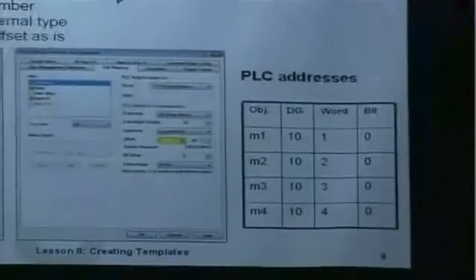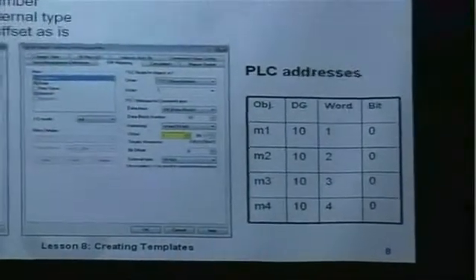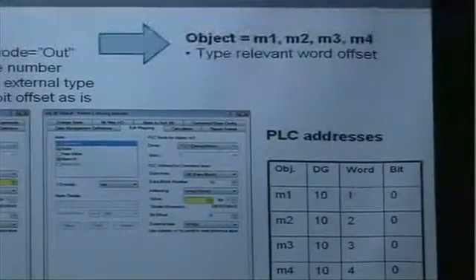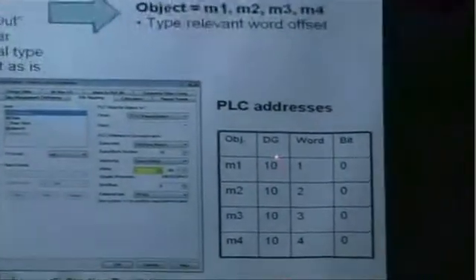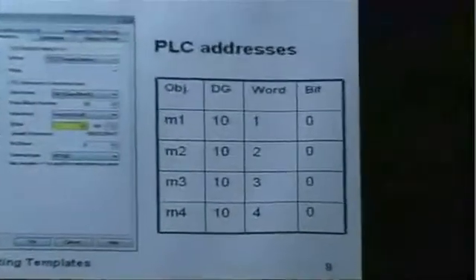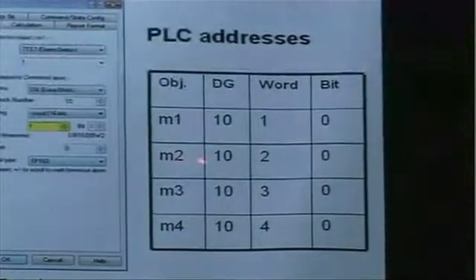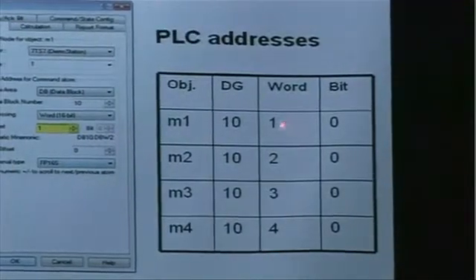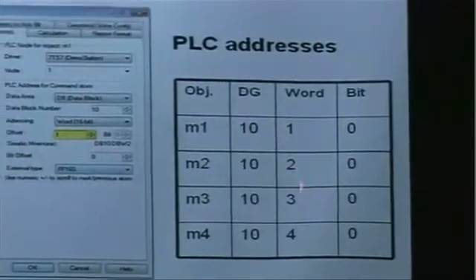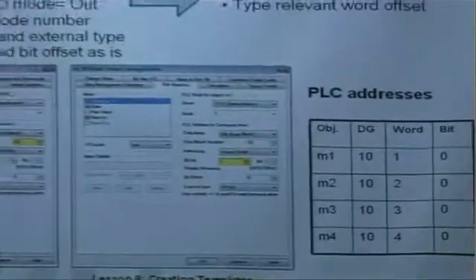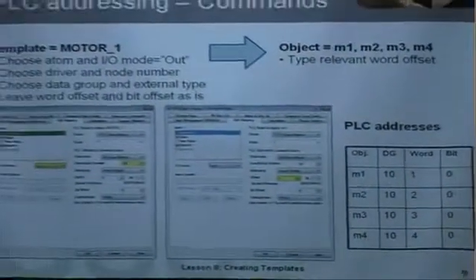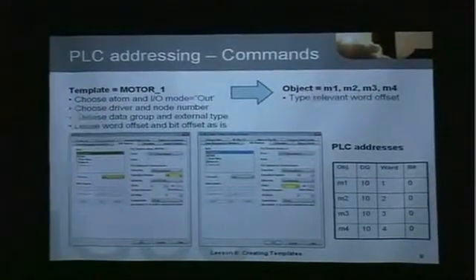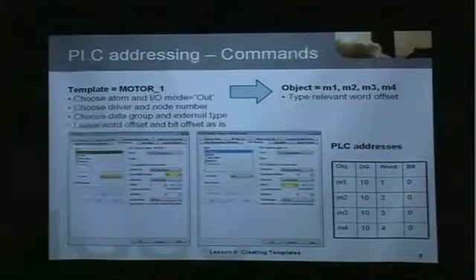If we look at four different motors all based on the same template, the PLC addressing would look like this. We have data block 10 as the common property set in the template, and then we assign a word offset of one for each of the four motors — word number one, two, three, and four. Typically a command in IGSS will take up 16 bits in the PLC — so one word.